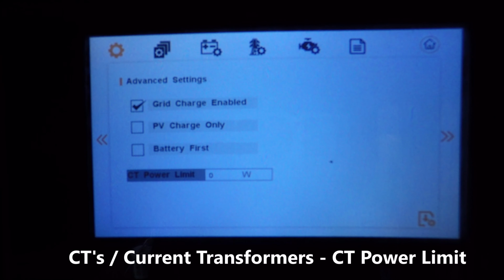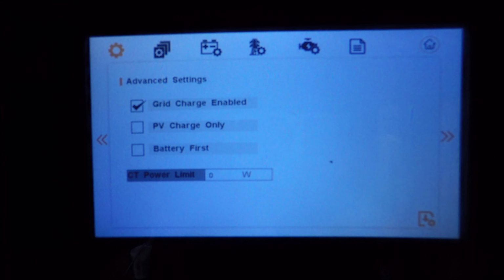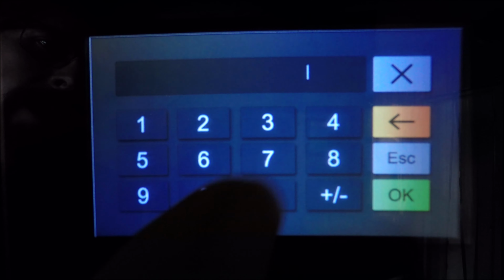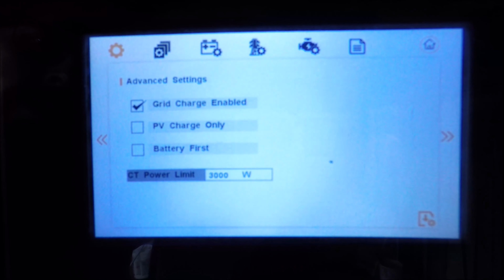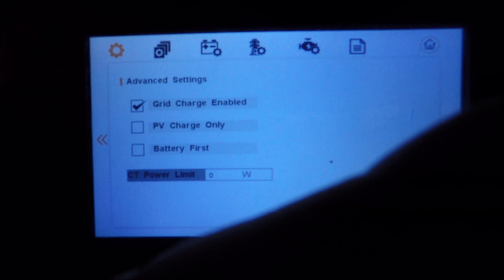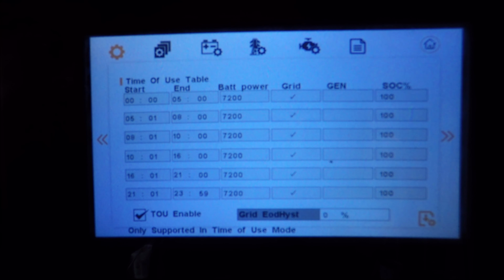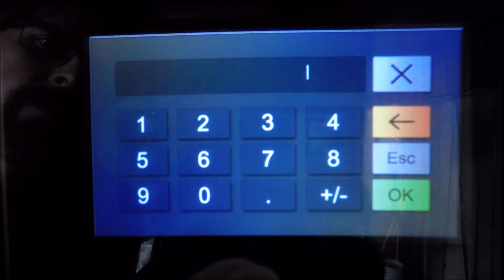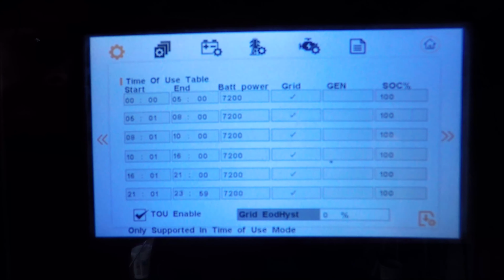CT power limit. If you are set up for grid feed, you can set how much power can go to the grid from the inverter. So for instance, it's a 10,000 watt inverter. Let's say you only want to feed 5,000 watts to the grid and have 5,000 watts available for load. If you were feeding the grid, you would set that limit here at 5,000. This allows you to mitigate the capacity that's available when doing a grid feed. In my case, I don't want to feed anything to the grid, so we're going to make that 0. Save. Next. If we were doing a grid feed, we would set this grid hysteresis to 5 or 10%. Because we are doing no grid feeding, mine is set to 0.